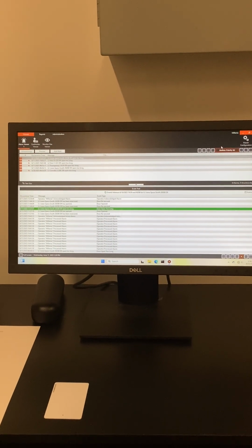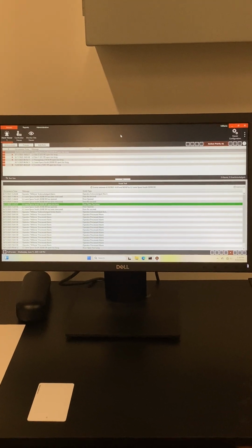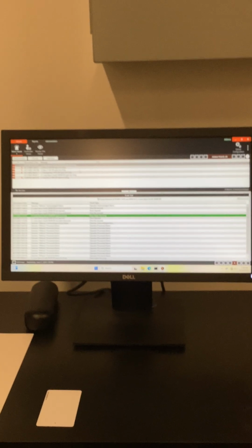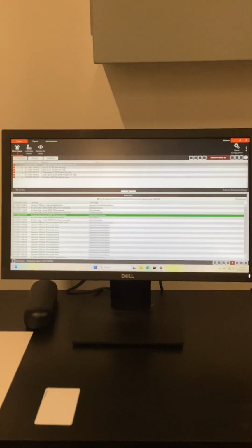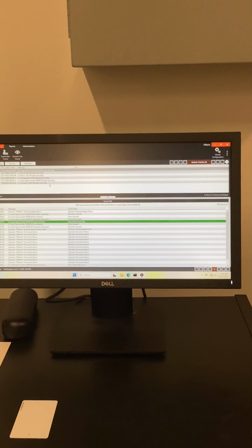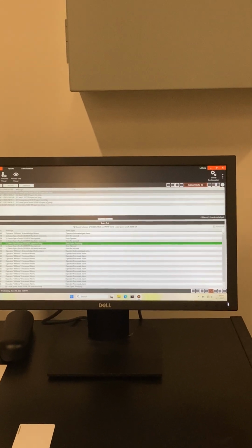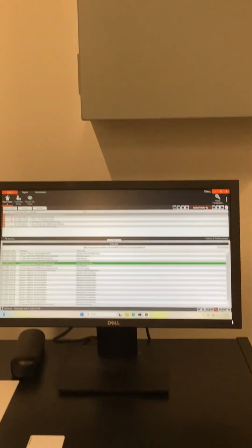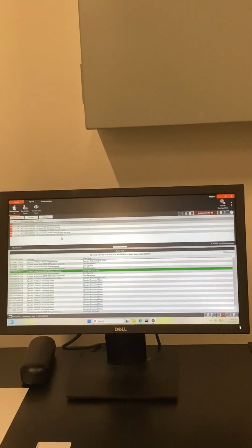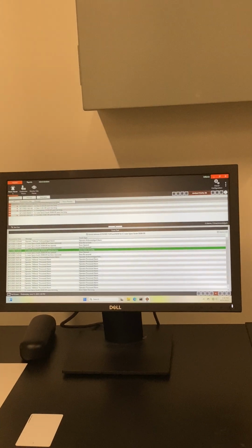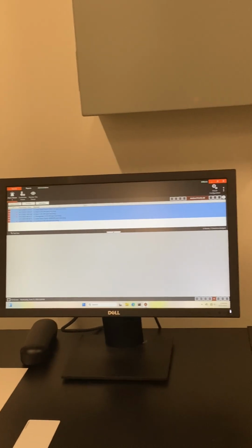Okay. Are there any in there that are, well, I assume it's all up for speculation, but say nuisance alarms? Alarms that I don't care about, alarms I don't want to get that are just going to bog me down? Just your door open too long. But you really don't have to do anything with it. It's just going to keep cycling. We have some systems right now where we pulled in way too many points of information that we don't want to see, and literally 100 errors a day. It's like a full-time job just clearing them. You can do it to where you don't have to do individual ones. If you go down here and right-click, force process, it mops them all up. It all clears.